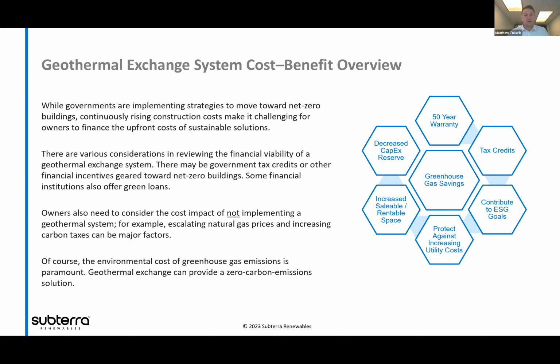And that's because of a few things. One we've already discussed is the energy savings, so we're paying less in utilities by removing a cooling tower particularly, which works on evaporation. You need to add more water and chemicals to it. We've reduced some of those consumables. And then the big thing a lot of folks don't generally think about, but is a very large benefit, is the reserve repair and maintenance.